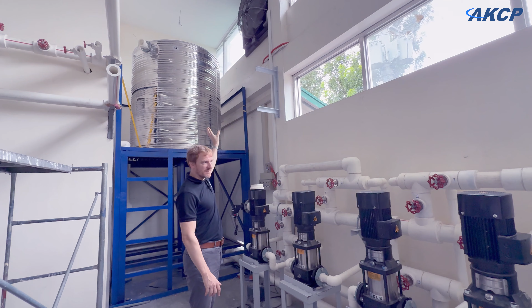If we run pumps in series, then we will get an increase of pressure but the same flow rate. And when we run pumps in parallel, then we will get an increase in flow rate but no increase in pressure. So depending on the demands of the facility, we can actually reconfigure this to run in different ways. These pumps are used in conjunction with the large tank you see behind me. So this tank will be kept cold by our chiller that's outside.